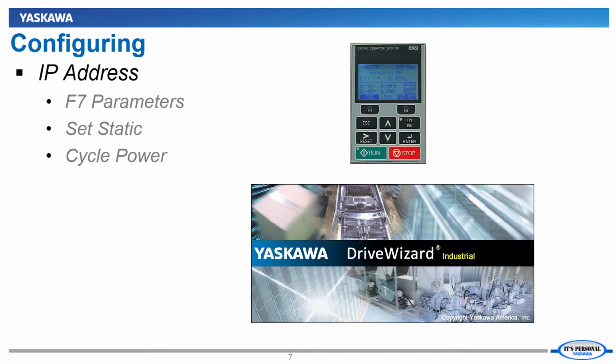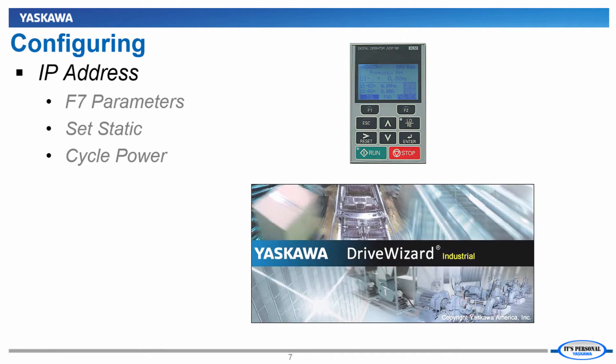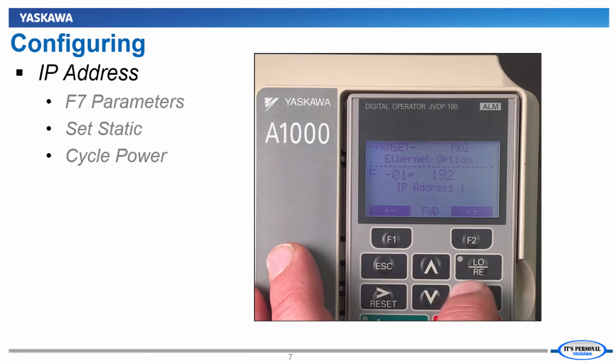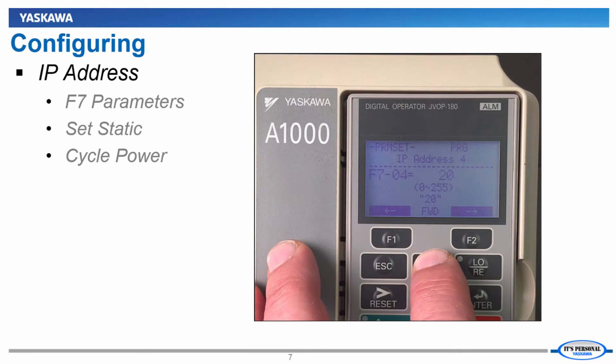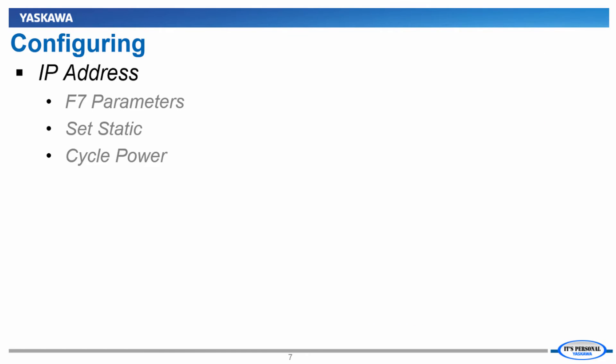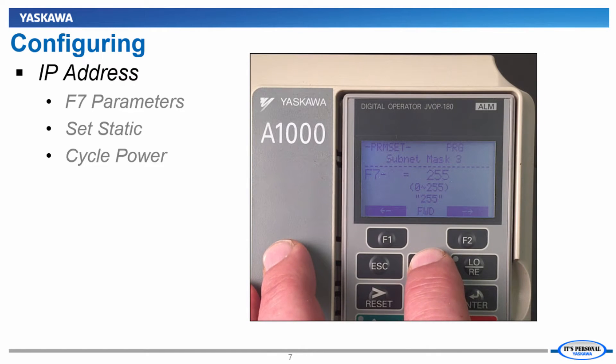Using the keypad or DriveWizard software, set the option card's IP address, which we'll set to 192.168.1.20 for this demonstration. Repeat the steps for Subnet Mask and Gateway if needed.